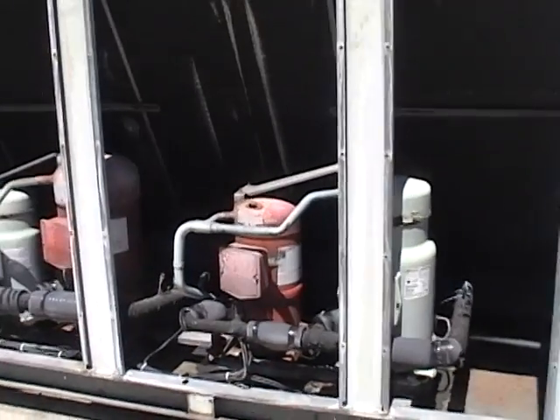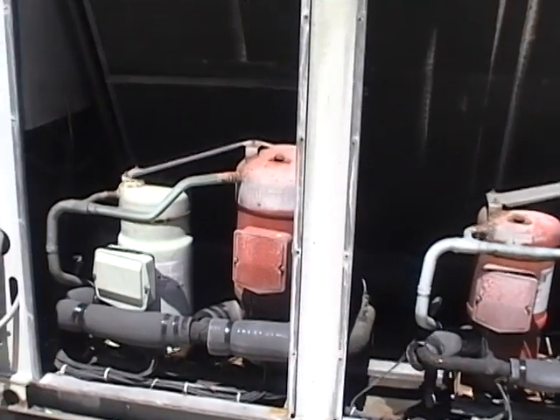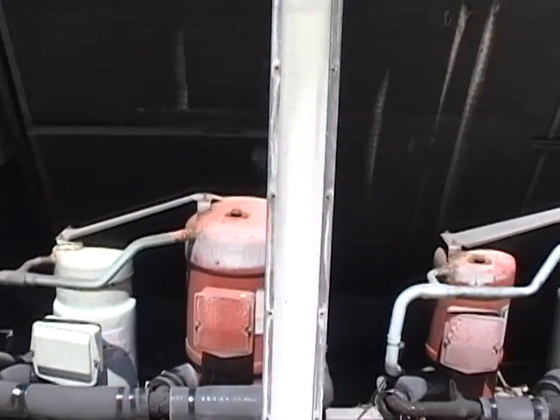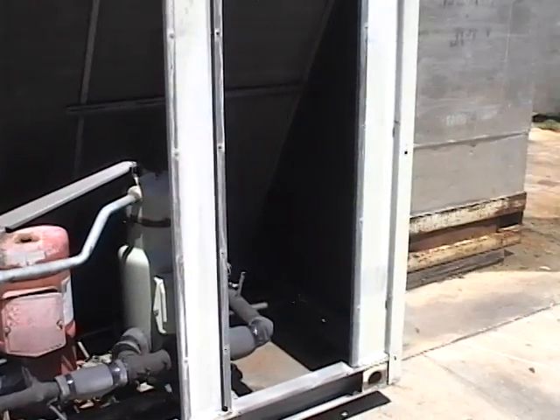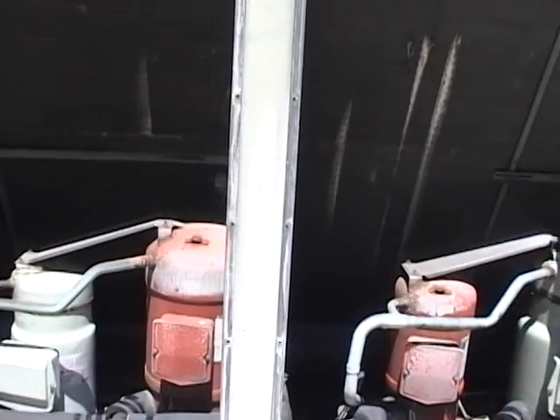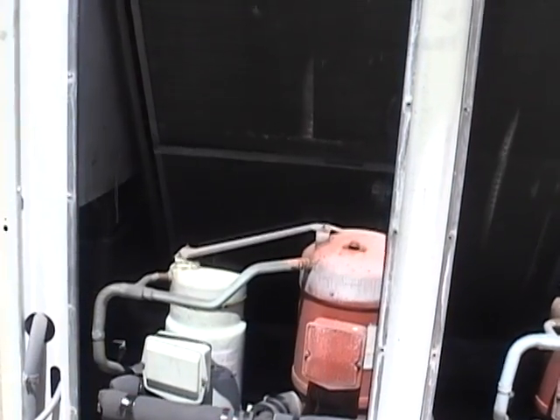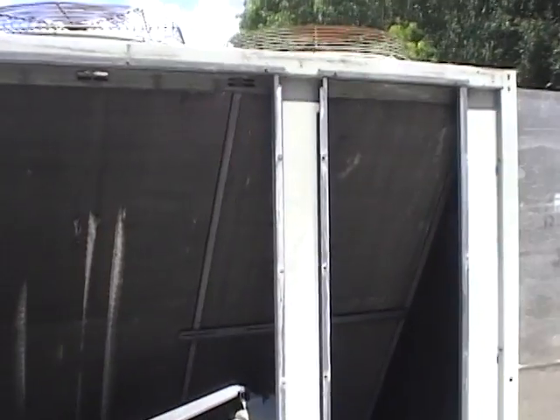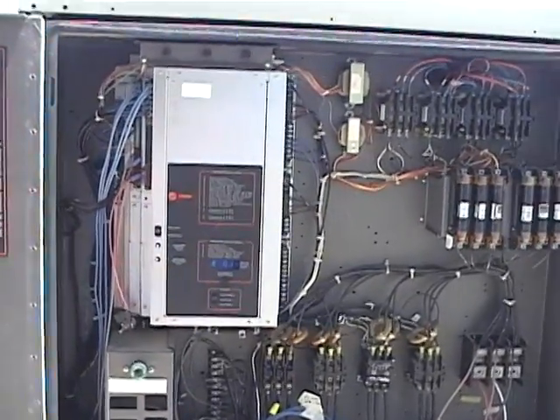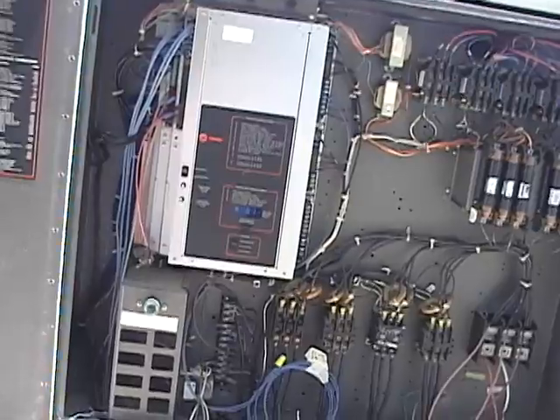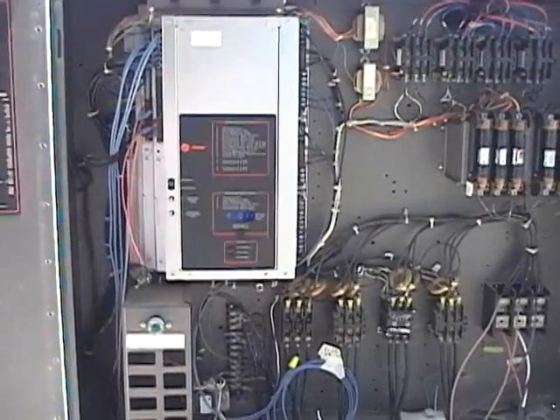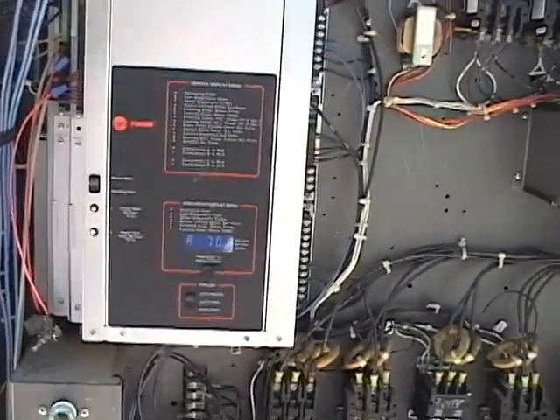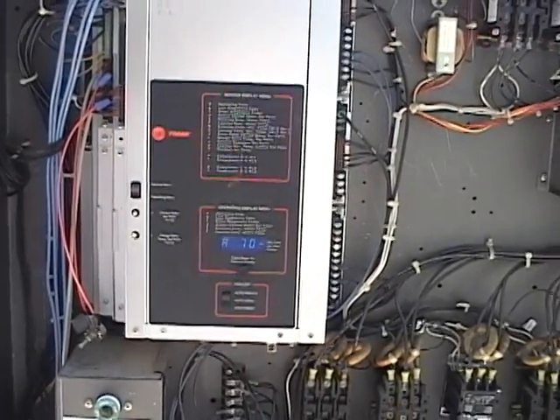Here you can see the compressors. And the condenser coil. The guards for where the compressors are, we just took them off just to show you the compressors with the unit running. Once the unit is plugged in, the 110 and the 480 volt is turned on, you'll notice that your annunciator panel will start to give you readings.